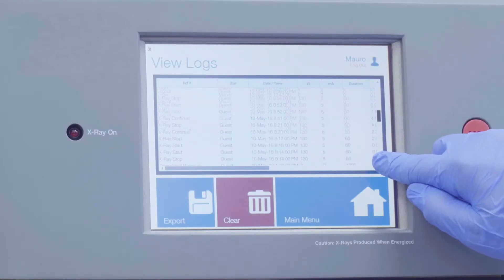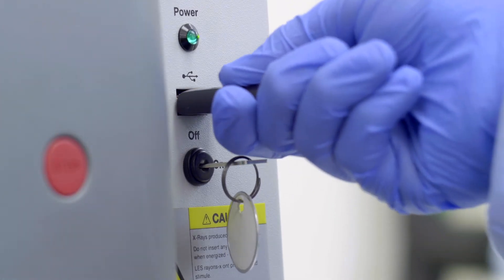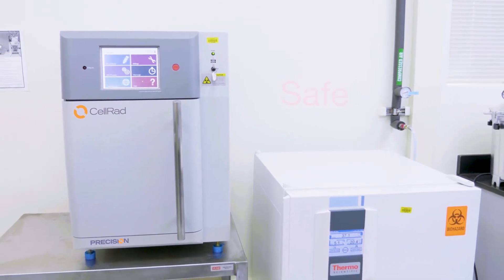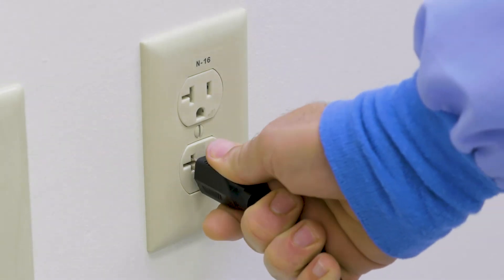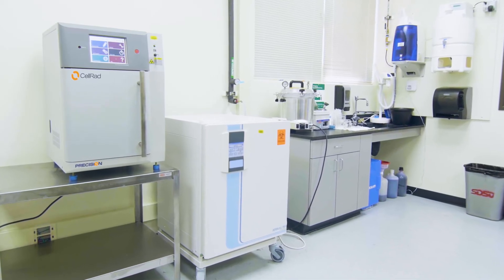Complete exposure history is stored and can be easily reviewed on screen or downloaded to a USB flash drive. CellRad is fully shielded and exceeds FDA radiation safety standards. It is self-contained and has no external components, requiring just a single standard electrical connection. No additional facility connections or valuable floor space is needed.